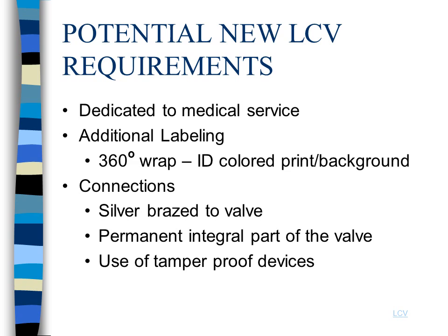They have since changed their mind on that, and they now require the use of tamper-proof devices. Tamper-proof devices are designed to thwart people from changing fittings from one gas to another.